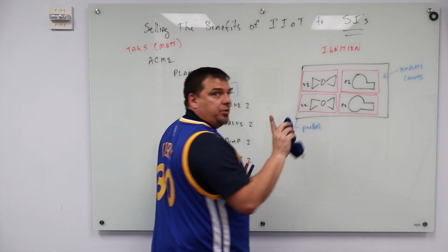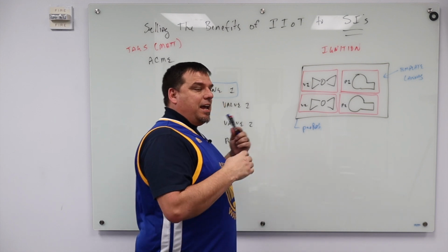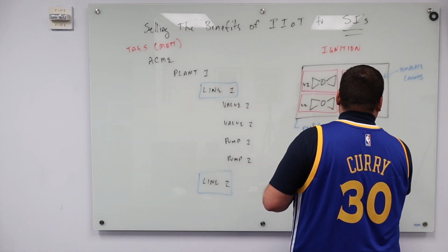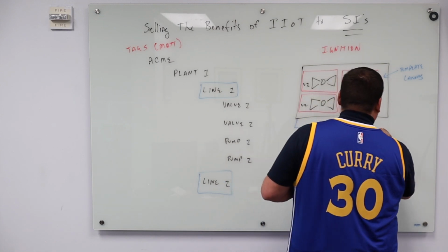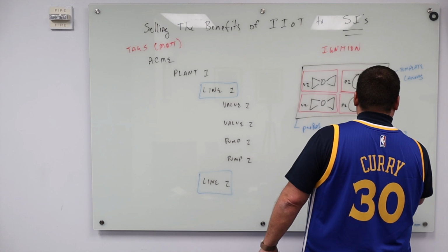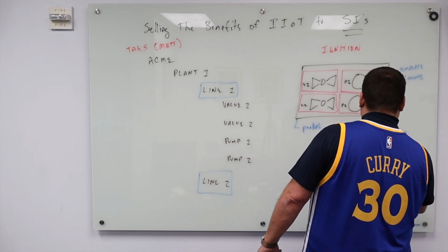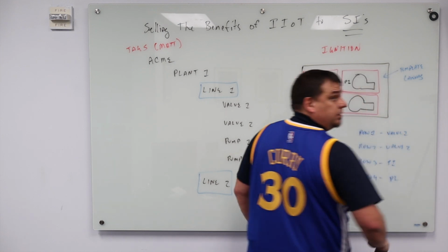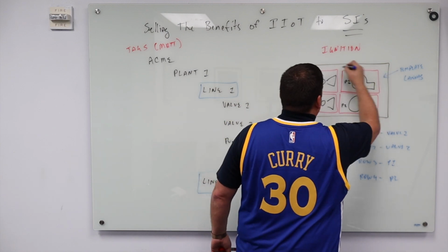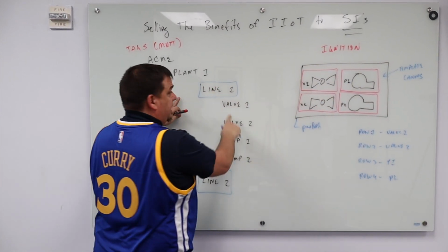What we've also done is there's a template canvas sitting on top of the window. That template canvas is basically a data set. It has a data set that has a row. Row 1 would be all the information for valve 1. Row 2 is valve 2. Row 3 is pump 1. And row 4 is pump 2. Now, that data set running inside this template canvas tells us which template should go where and where it should get its values from.